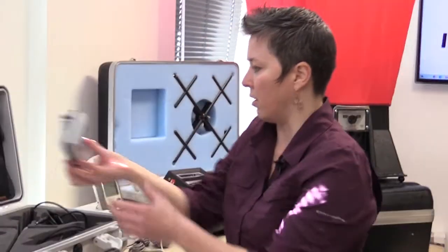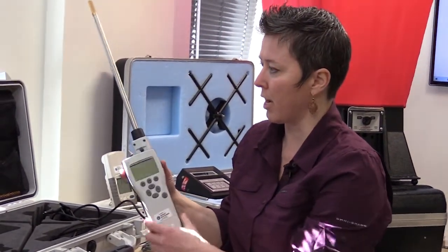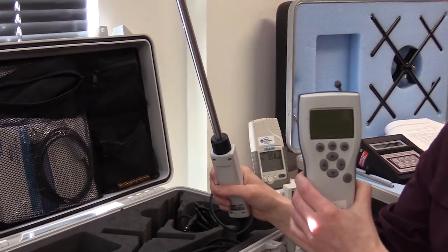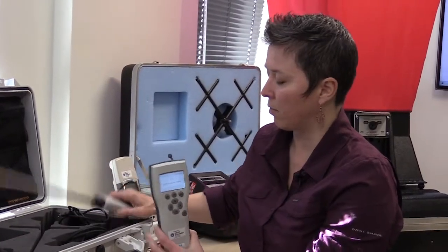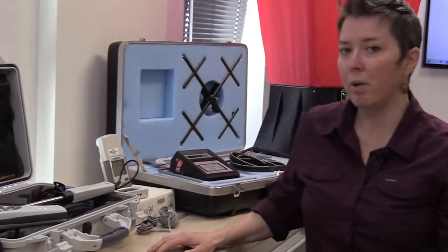So you can do spot measurements. This instrument here is a spot probe for measuring CO2 levels. It can also do CO, and a very useful, highly accurate instrument. Now, for getting a good picture, though, of what CO2 levels are happening in your building, you want to do measurements over a sustained period of time so that you can see how effectively your ventilation system is working to keep the air diluted.